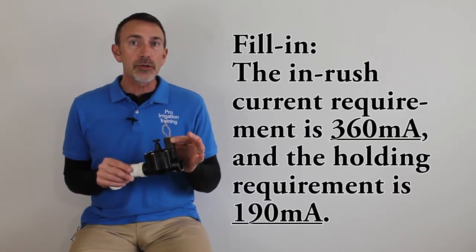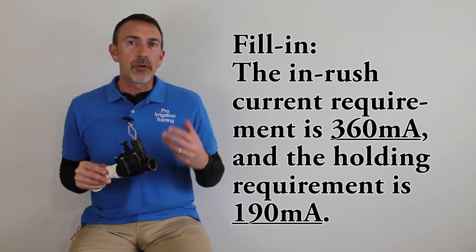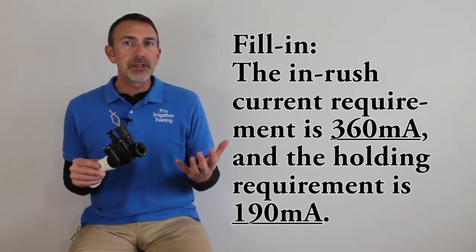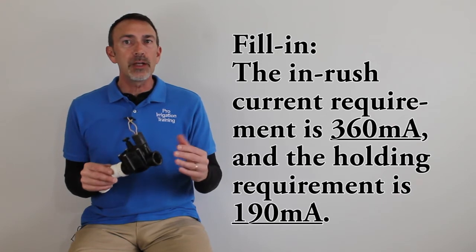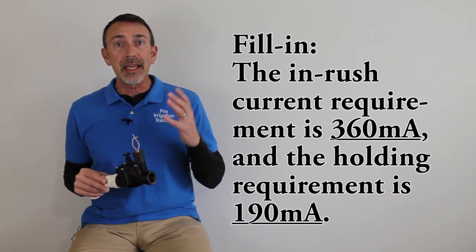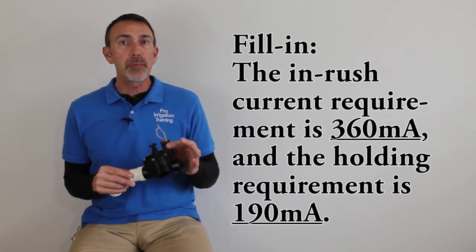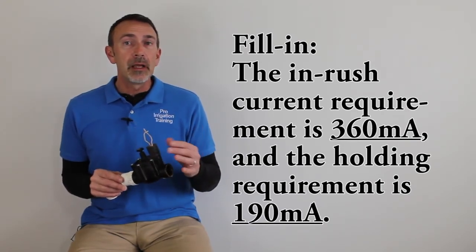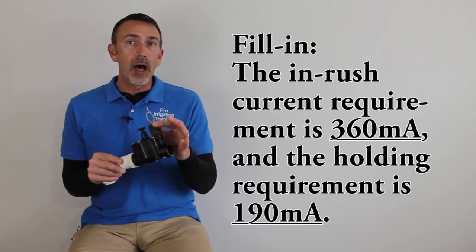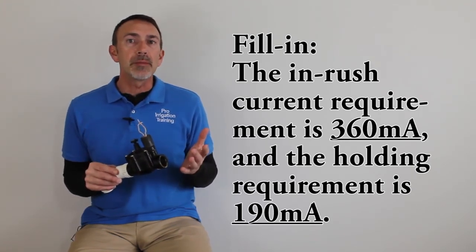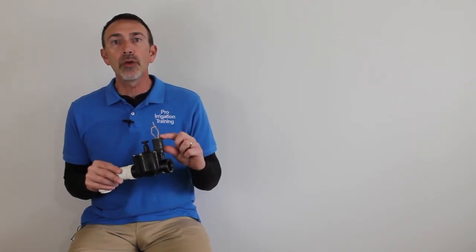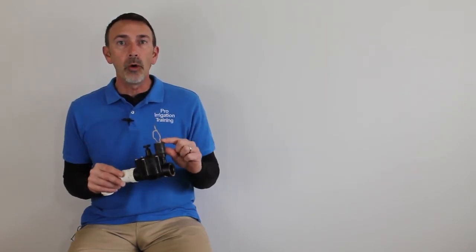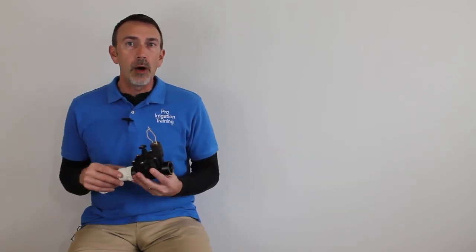We have an inrush requirement, which basically means that for any electrical appliance or tool, it takes a little bit more electricity when you very first turn something on, and that's called the inrush requirement. And for the typical solenoid, that's around 360 milliamps, and then the operating or the holding current is around 190 milliamps. So as you can see, it takes a good bit more to open this solenoid up as it does to hold it open across the period of time that this zone is going to be running.